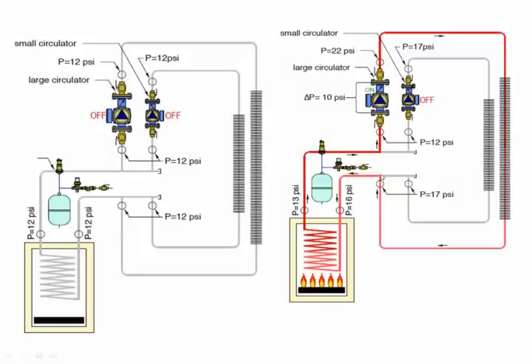We're delivering heat to our zone. We're coming back around. We get to this T here. Now the water wants to go somewhere. It can't go this way because we have a check valve on the top side of this pump, okay? So it continues on its flow, losing pressure through the heat exchanger of the boiler back up to 12 psi, okay? All right, everything's fine and dandy. Everything's happy so far. People are getting heat in this zone.